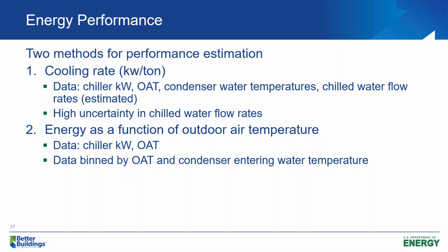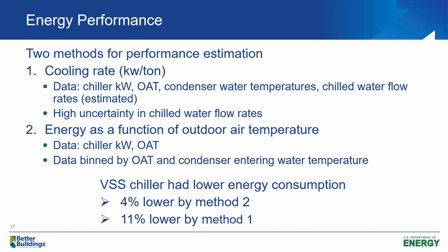So when we look at these two methods, the variable speed screw chiller had the lowest energy performance. By method 2, it was estimated about 4% lower. Method 1, about 11% lower. So there's a range, and depending on the application, you're going to get different performance too, depending on how many hours and the different loads that you're operating in.